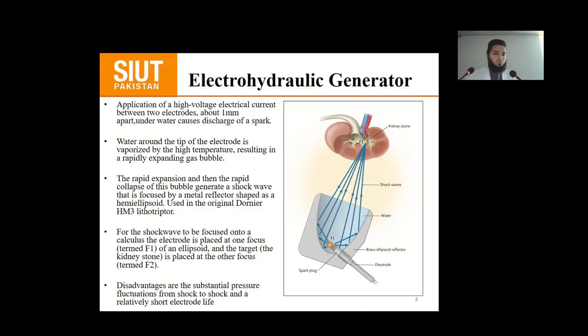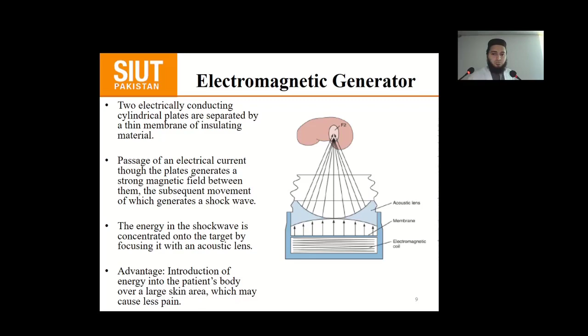As far as the electromagnetic generators are concerned, there are two electrically conducting cylindrical plates, separated by a thin membrane of insulating material. Passage of an electrical current through the plates generates a strong magnetic field between them, the subsequent movement of which generates a shock wave. The energy in the shock wave is concentrated onto the target by focusing it with an acoustic lens. The advantage is the introduction of energy into the patient's body over a large skin area, which may cause less pain. Here in the diagram we can see that there is a lens which focuses the generated shock waves at the same point, which is termed F2.